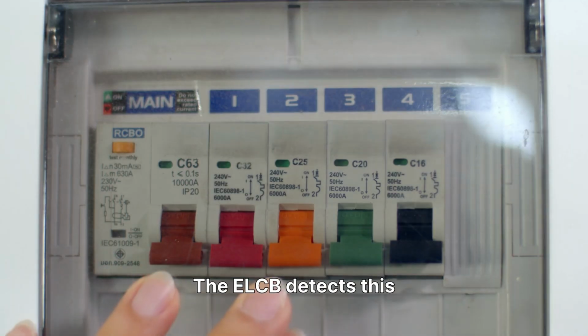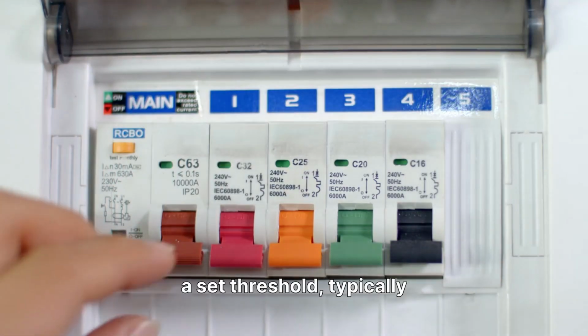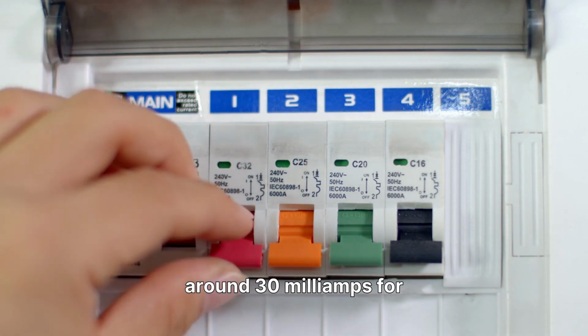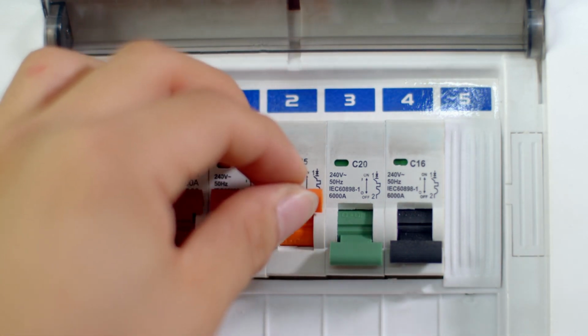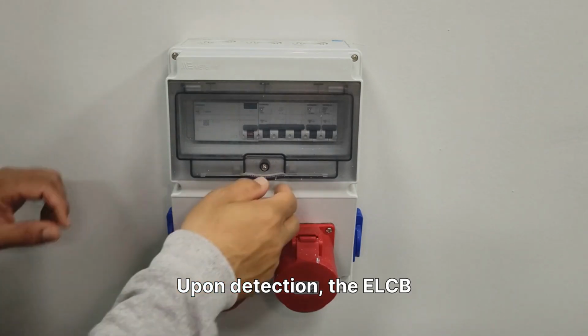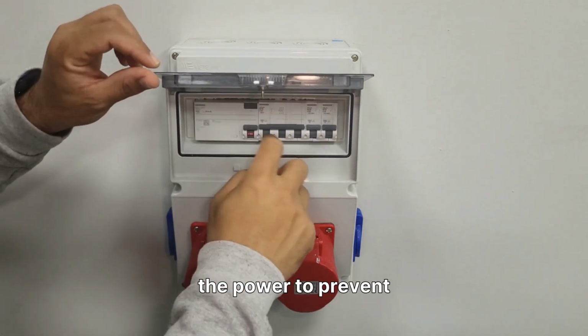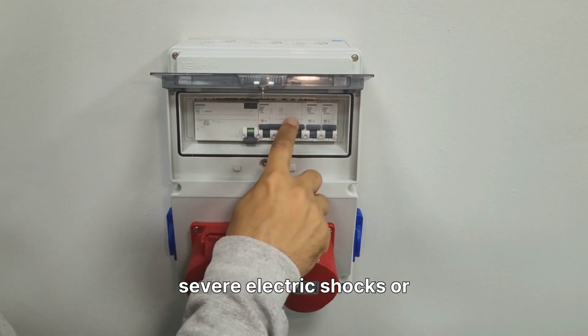The ELCB detects this imbalance when it exceeds a set threshold, typically around 30 milliamps for current-operated models. Upon detection, the ELCB trips instantly, cutting off the power to prevent severe electric shocks or fires.